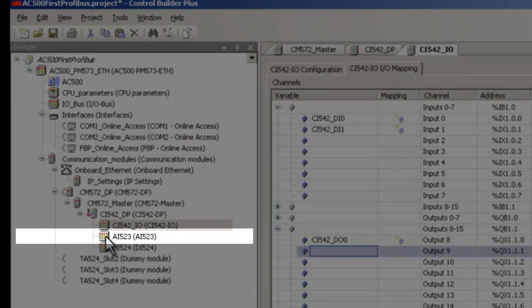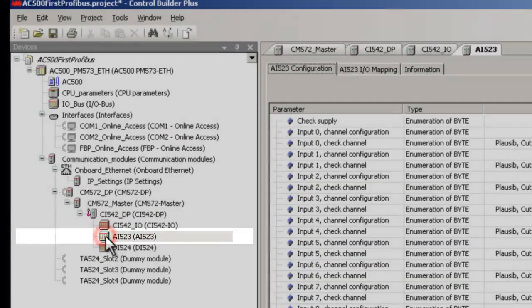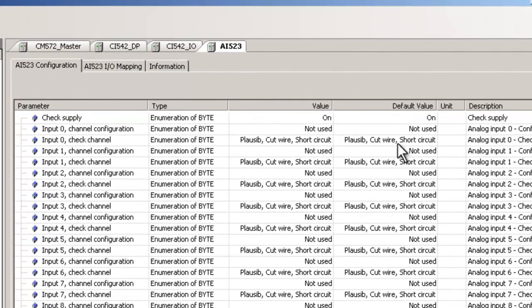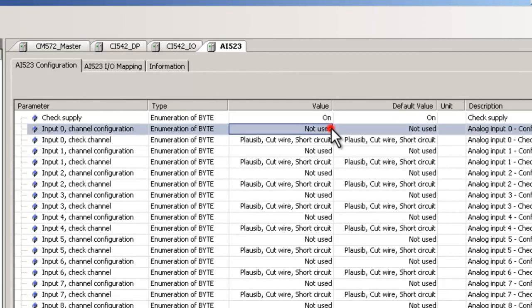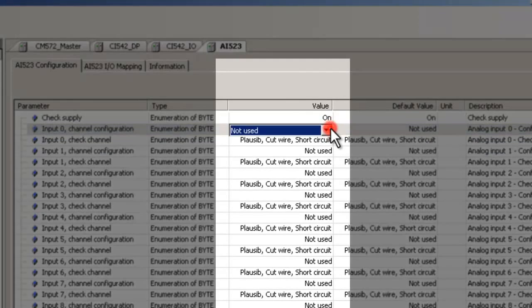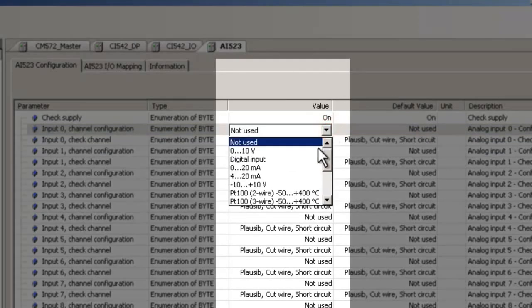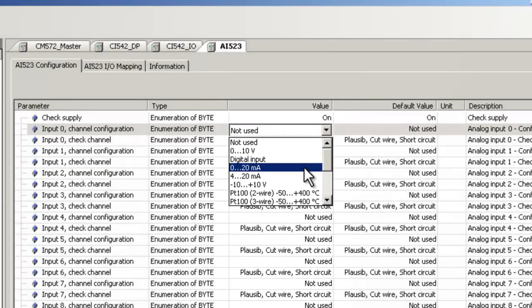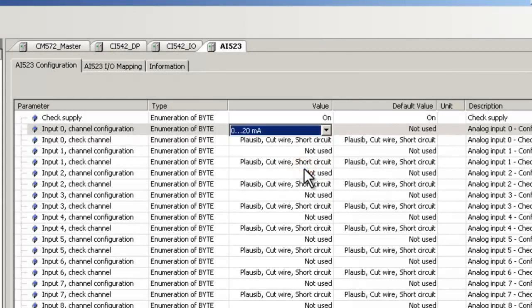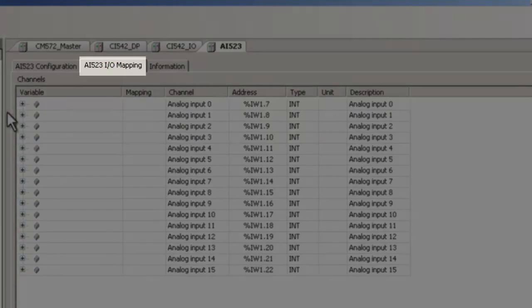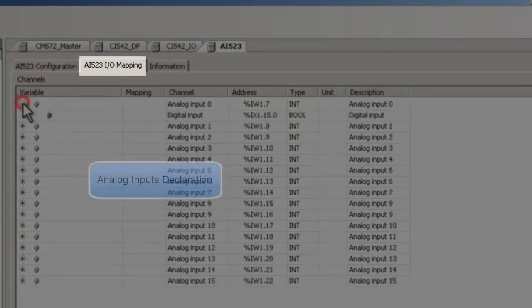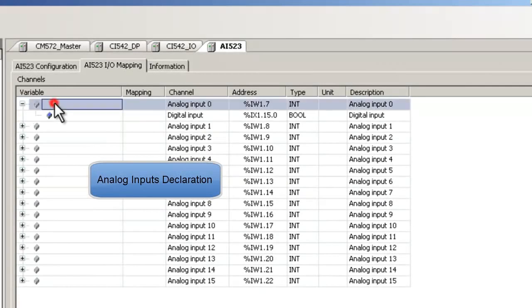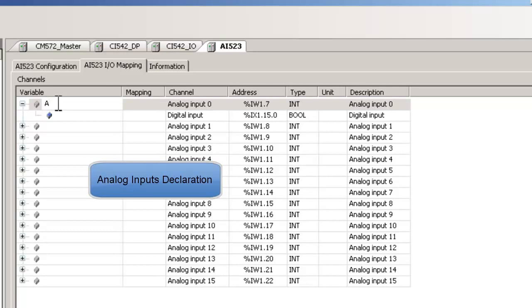Similarly, we would continue with the configuration for the analog module AI523. In the AI523 configuration tab, we have to modify the default channel settings according to actually connected signal types. In this example, channel 0 is wired to 0 to 20 mA signal. Double-click on the parameter field and in the column value, select the corresponding parameter from the drop-down list. After that we create a symbol for the signal. Click on Tab AI523IO Mapping. Here we define symbol for the analog input 0. Just for easy recognition, we use the module name in the symbol as a prefix.